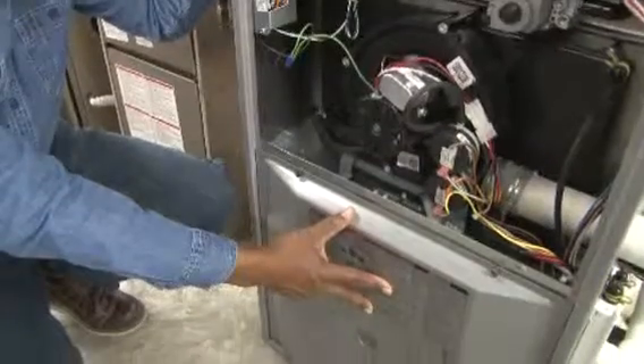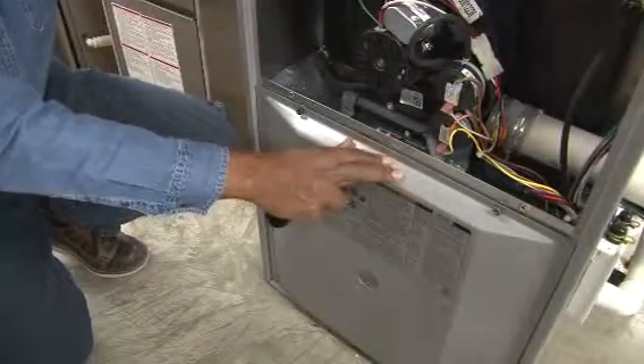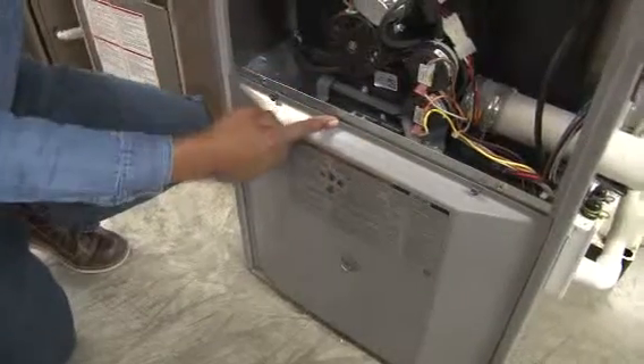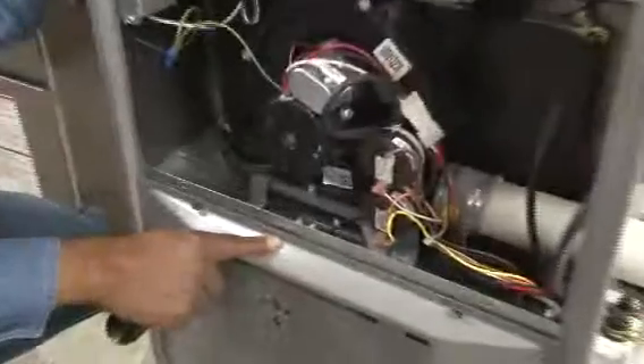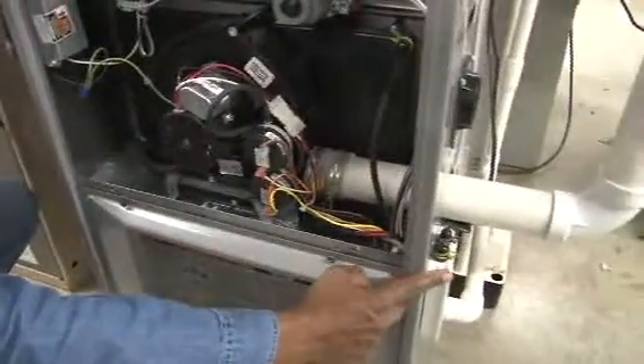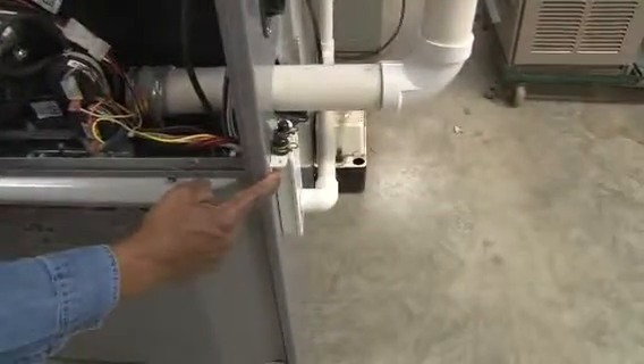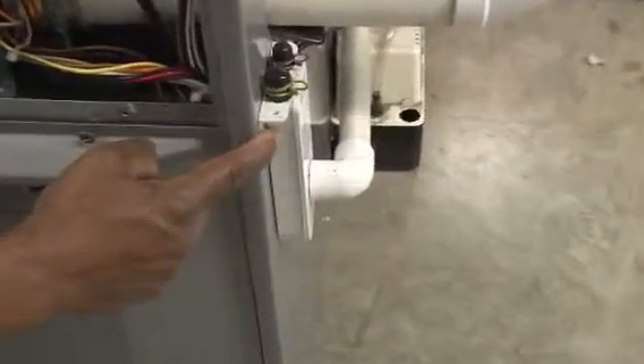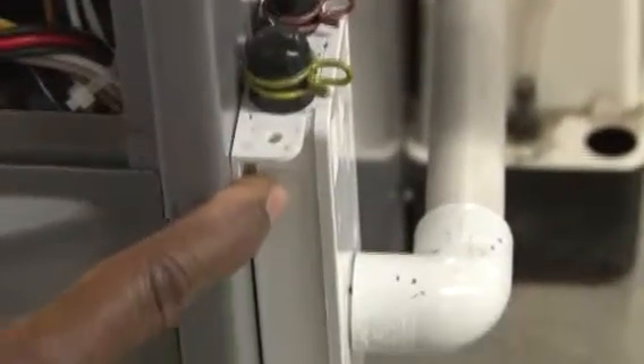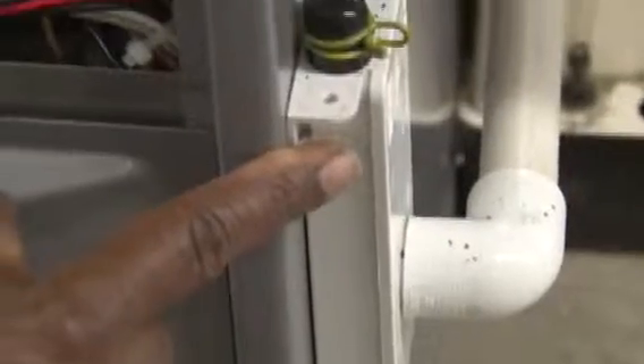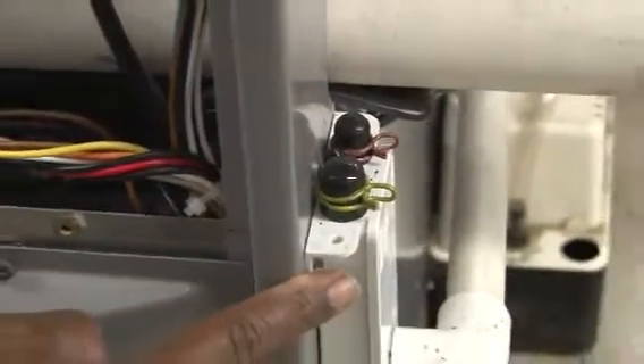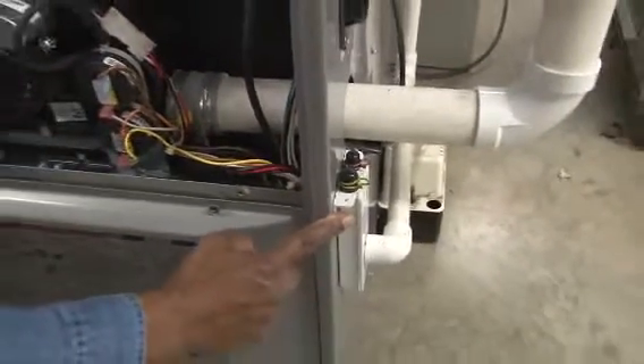The other part is the lower portion of this furnace, which is the blower section. And to run this, the blower has to be on, and there's a switch you cannot see, but it's behind the door to allow the system to operate when the door is closed. If I open the door, it will de-energize the system to keep it from operating, for safe conditions. And on this other side of this furnace is the collector box to collect the condensate that will build up inside of the furnace based on the heat it's extracted from the flue gases. As it extracts, it will condense the flue gases back into a liquid from a gas, and then it will drain to the floor drain.